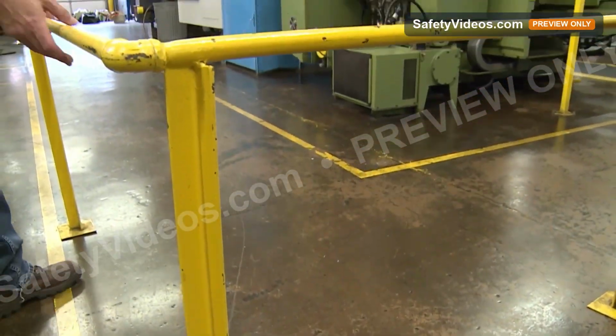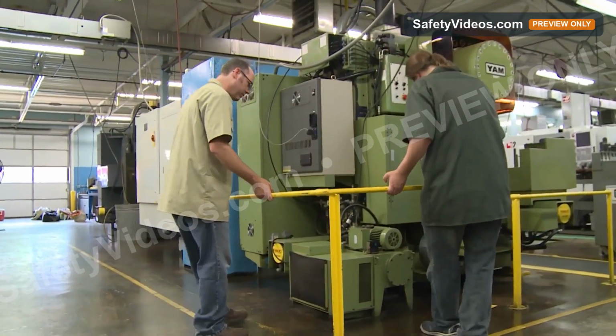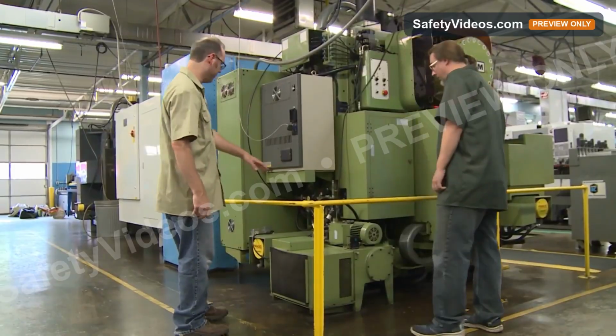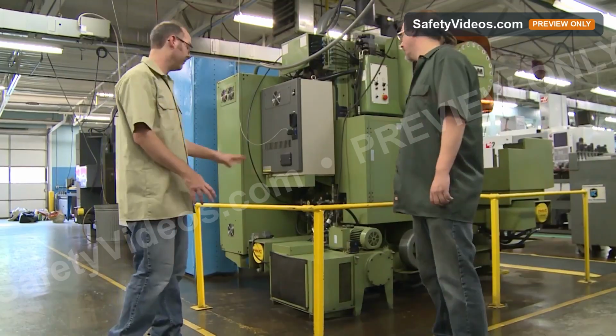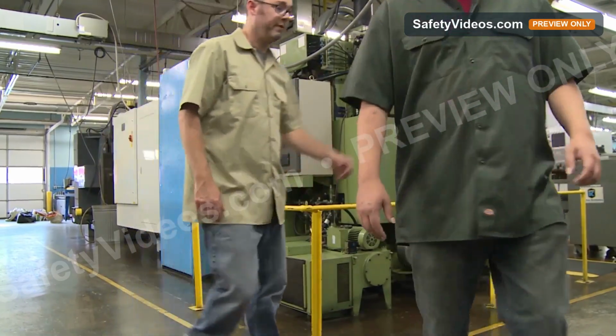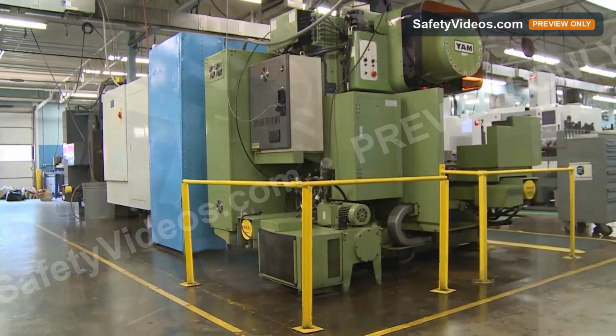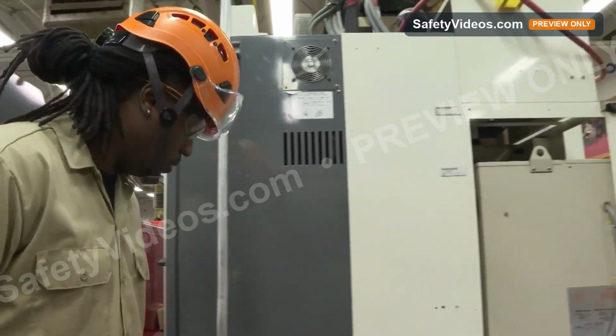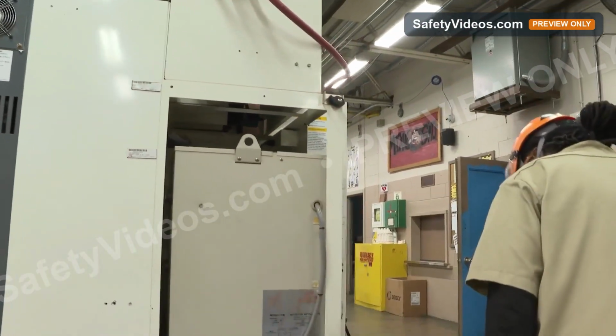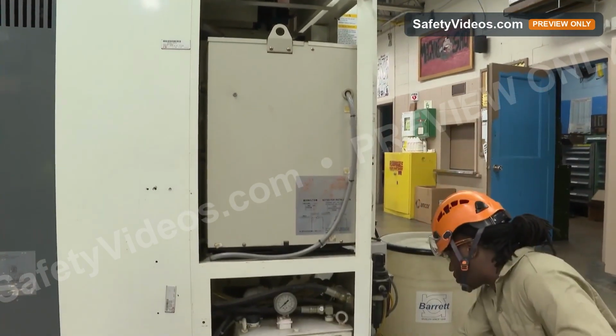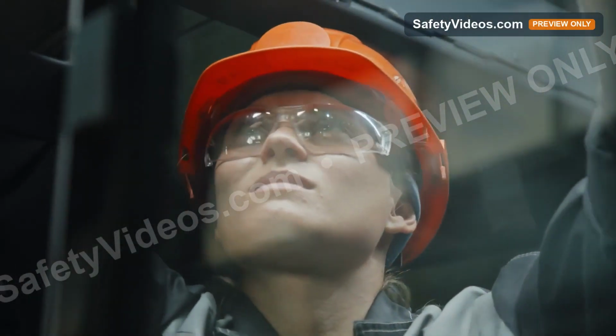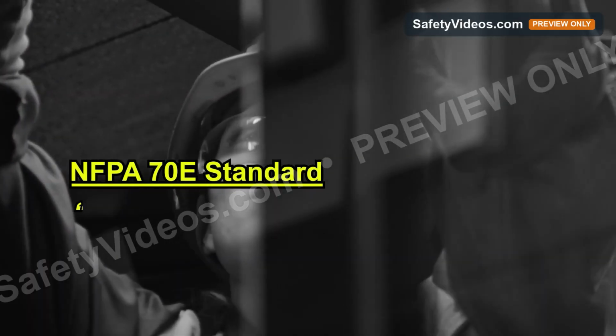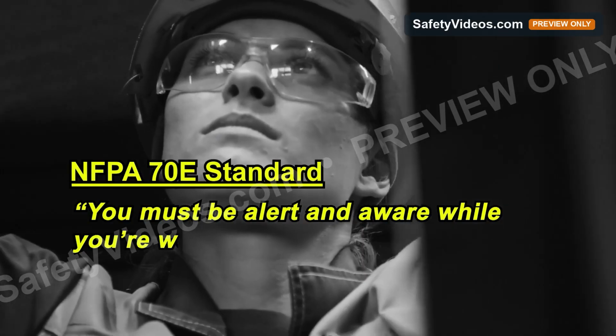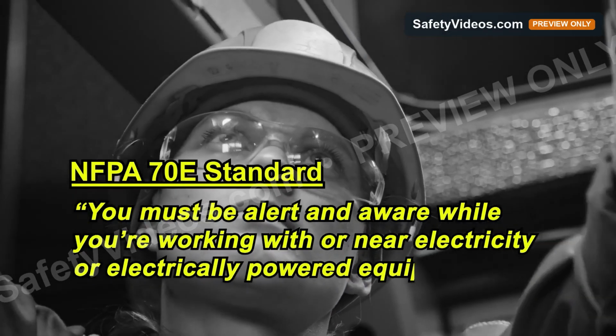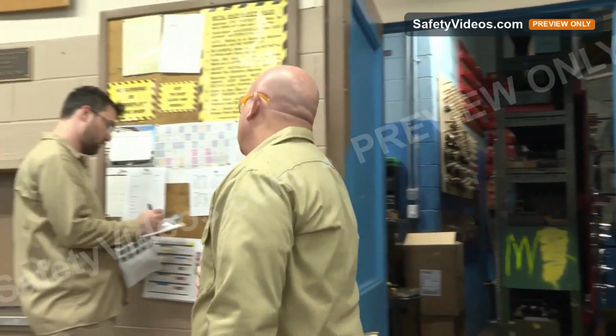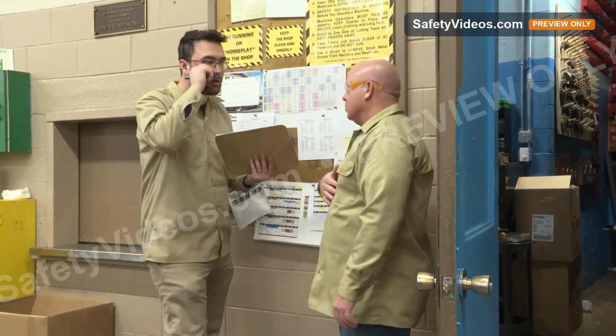The NFPA 70E standard also lists physical or mechanical barriers that can be used as a protective measure when you're working around exposed energized electrical conductors that operate at 50 volts or more to prevent any accidental contact. It's also essential to understand the procedural precautions you should take while you're working around electrical equipment that can help to keep you safe. For example, the NFPA 70E standard stresses that you must be alert and aware while you're working with or near electricity or electrically powered equipment. So if you're feeling tired, sick, or distracted, alert your supervisor immediately.